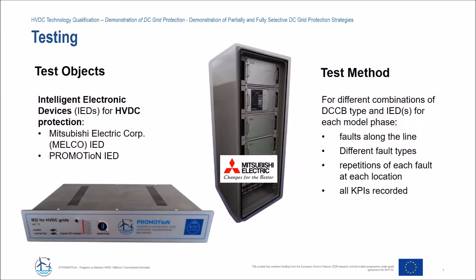The IEDs that were under test here were the PROMOTION IED developed within Work Package 4, but also a vendor-supplied IED. Some key differences between them is that the vendor-supplied one is using their state-of-the-art technology, and maybe the photo doesn't give you that good an impression, but it's a very different scale to the PROMOTION IED. And this is something that would be ready to be installed in a substation today.